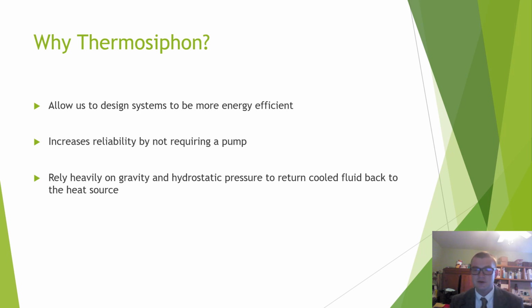Because it doesn't require a pump, it's very easily maintained, as there are no moving parts. The downside is that these thermosyphons rely heavily on gravity and hydrostatic pressure to return cooled fluid back to the heat source, making them trickier to design.